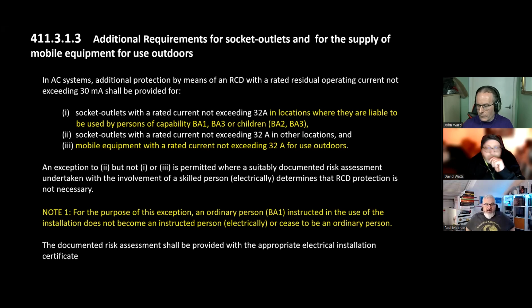That's your blanket. There is an additional note 1, that says for the purpose of the exception, an ordinary person instructed in the use of the installation does not become an instructed person. Now, that was an interesting one that was debated on the IET introduction. I have taken that as basically I can't instruct someone, for example, I've put you on a non-RCD socket for a fridge, but just don't plug anything in outdoors. That wouldn't be acceptable anymore, because they're not electrically minded enough to follow that instruction for the life of the installation.